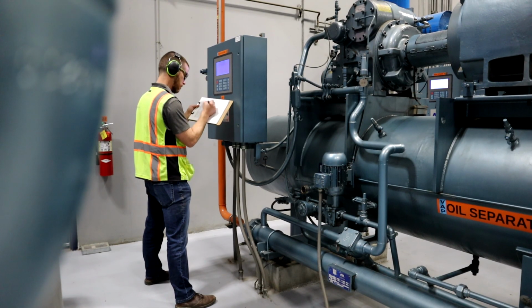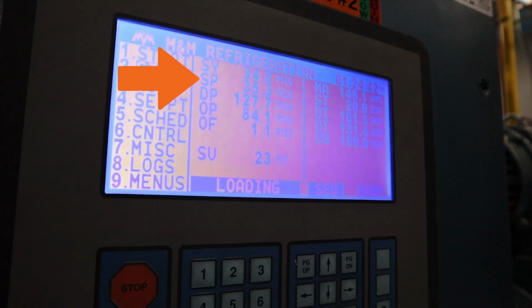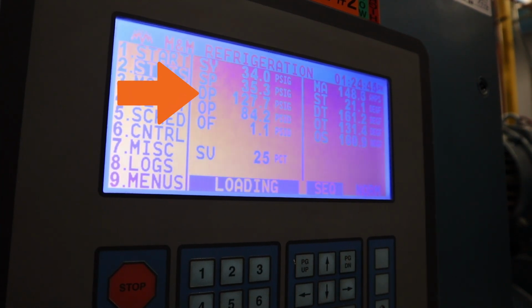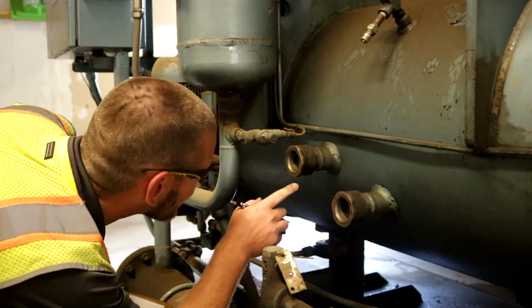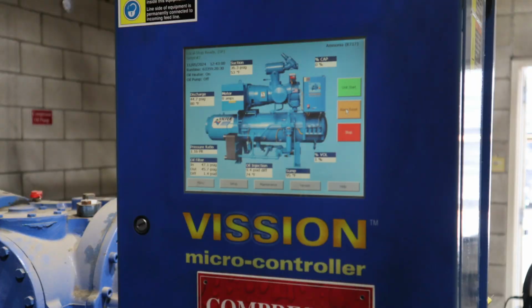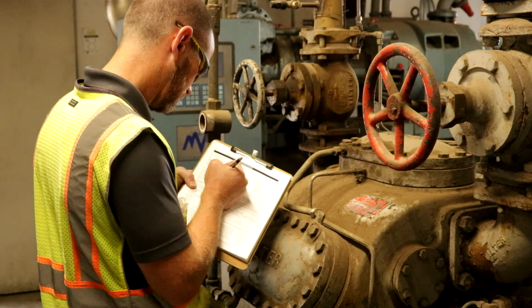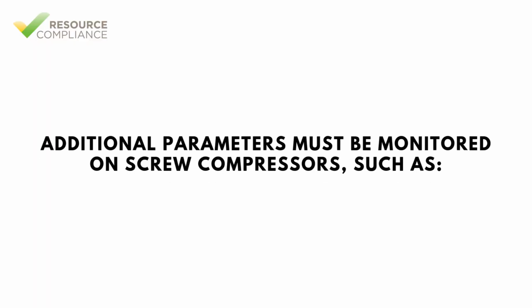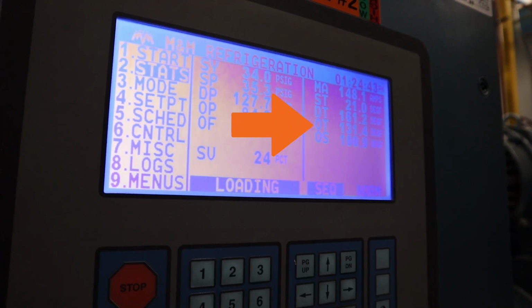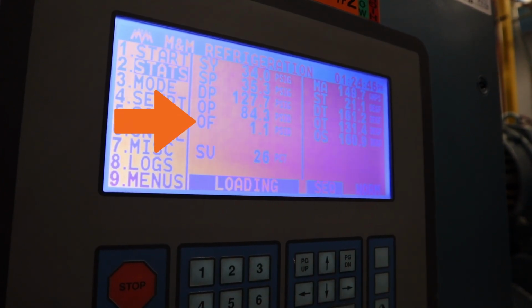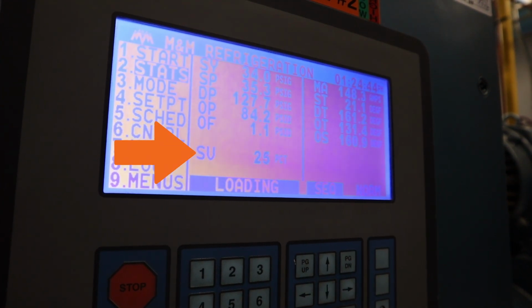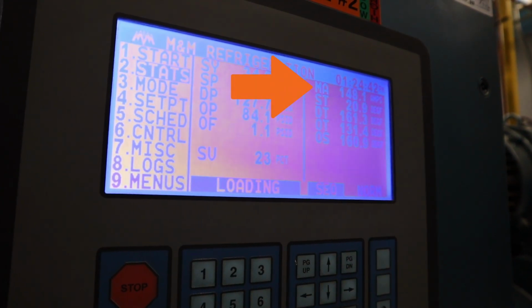Daily, the following must be monitored on all compressors: suction pressure, discharge pressure, oil level, oil leaks, alarms on control panel, and abnormal sounds and vibration. Additional parameters must be monitored on screw compressors such as oil temperature, discharge temperature, oil filter differential pressure, slide valve capacity percentage, and motor amperage.